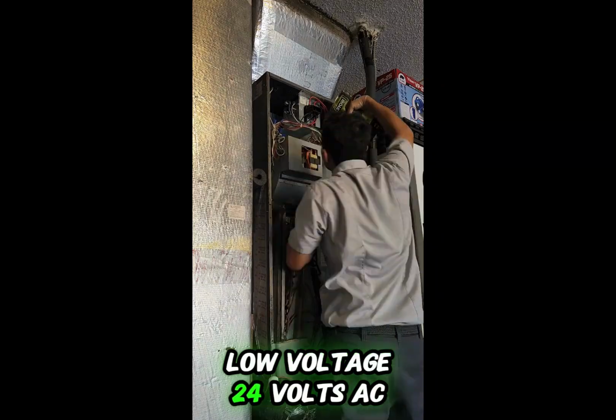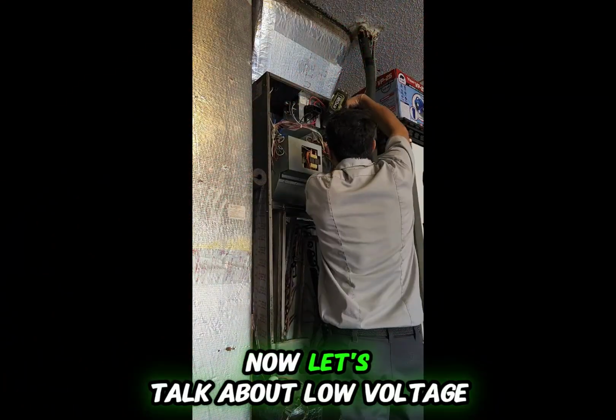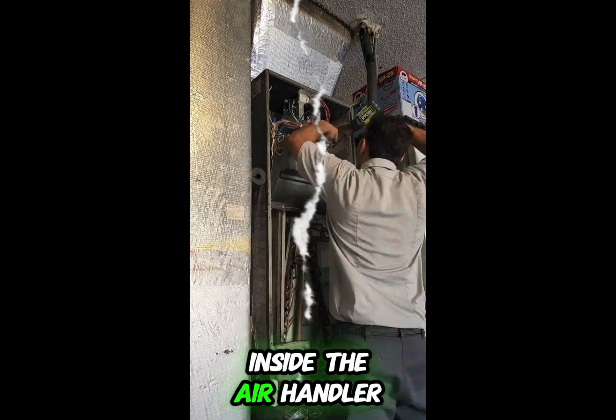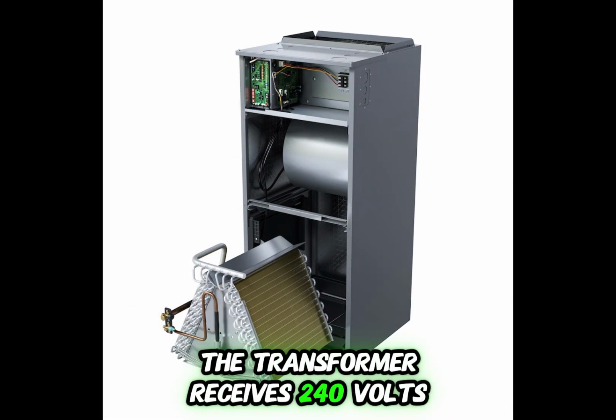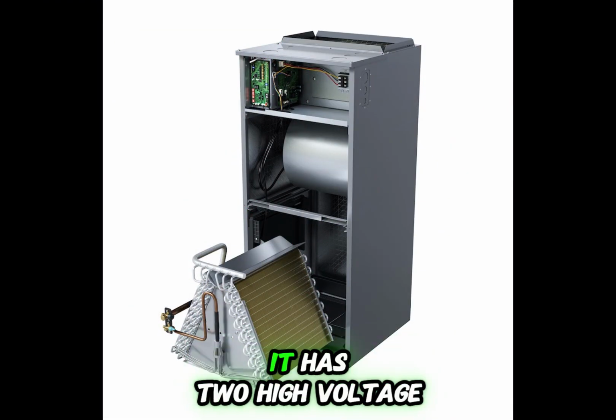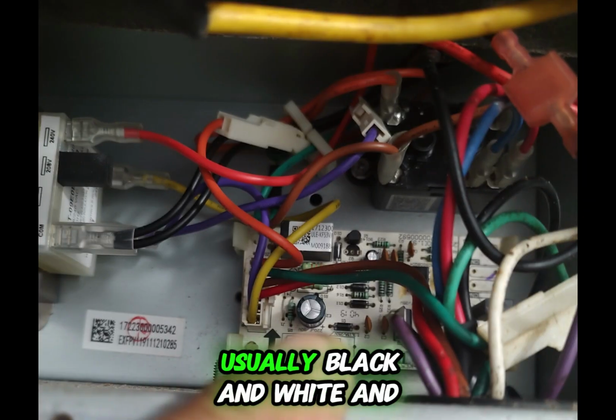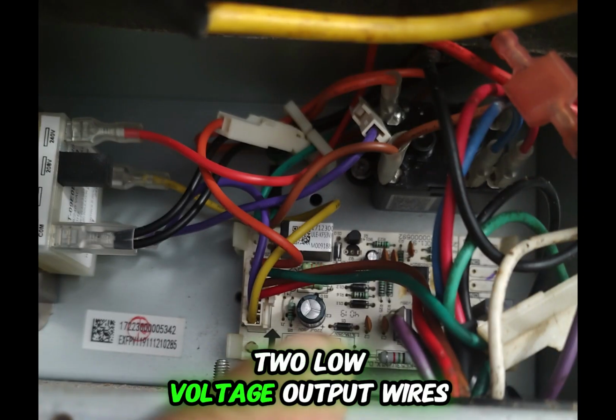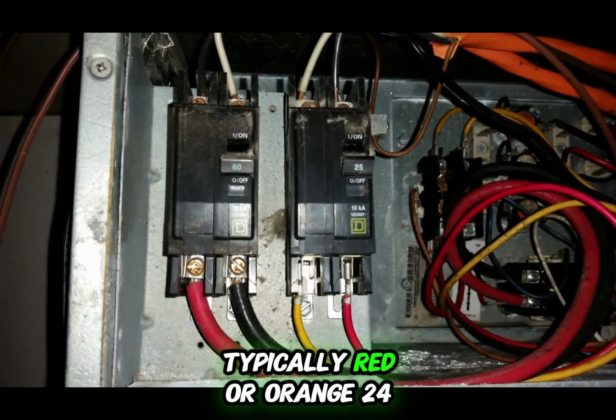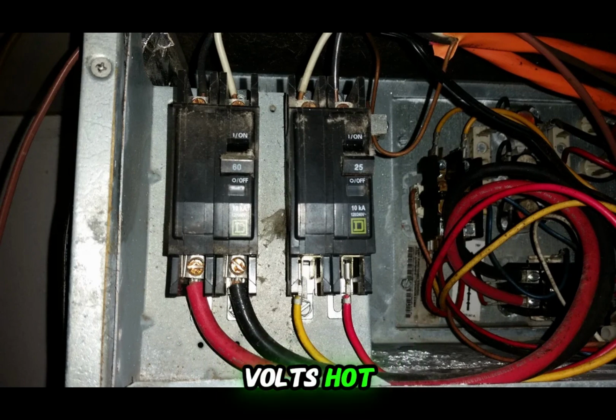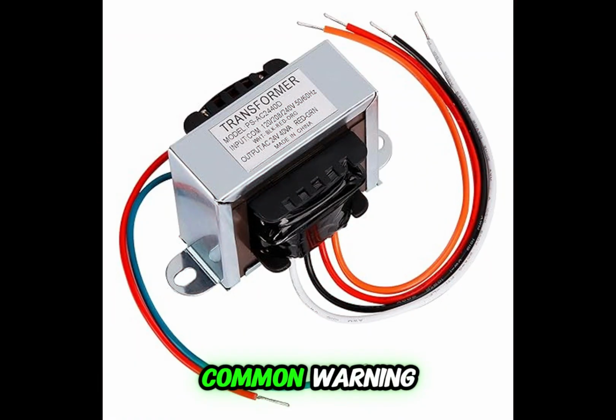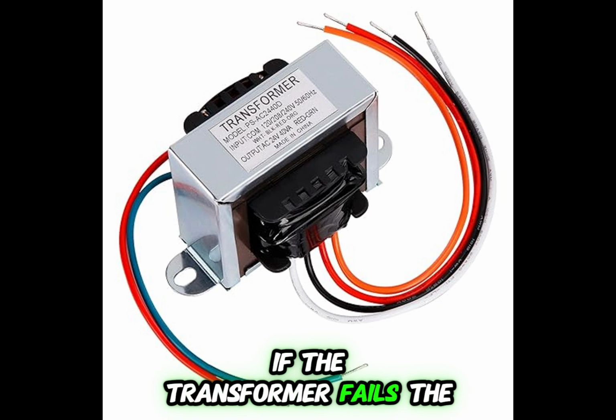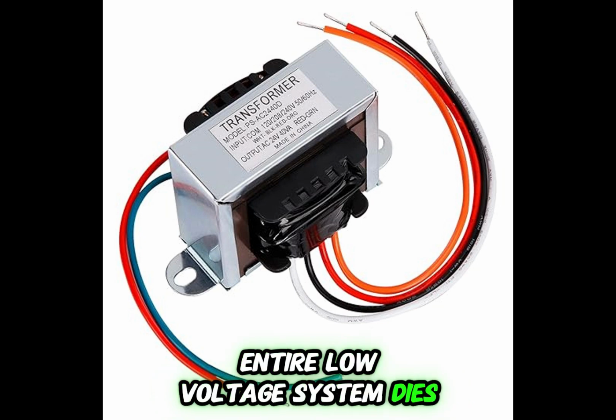Low voltage, 24 volts AC. Now let's talk about low voltage, the 24-volt control circuit. Inside the air handler, the transformer receives 240 volts from the internal breaker. It has two high-voltage input wires, usually black and white, and two low-voltage output wires, typically red or orange, 24 volts hot, and blue or brown, 24 volts common. Warning: if the transformer fails, the entire low-voltage system dies.